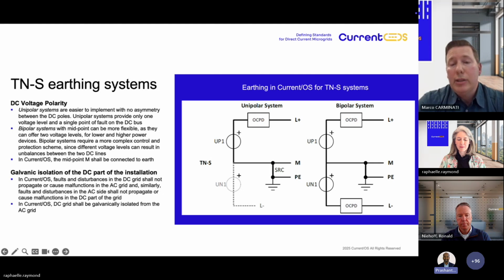So in Current OS, in order to reduce dramatically the risk of corrosion, we recommend the usage of the TN-S earthing system. A TN-S earthing system can be unipolar or bipolar. Unipolar systems, as you can see in the first figure on the left, are easy to implement, with no asymmetry between positive and negative, or midpoint earthed. But unipolar systems provide only one voltage and a single point of failure. Instead, bipolar systems with a midpoint, usually distributed, are more flexible, as they can offer two levels of voltages without any additional DC-DC converter in our system to supply medium, large, and small appliances or loads.